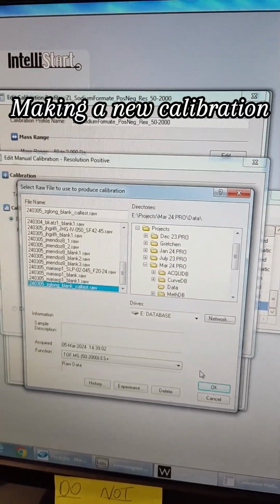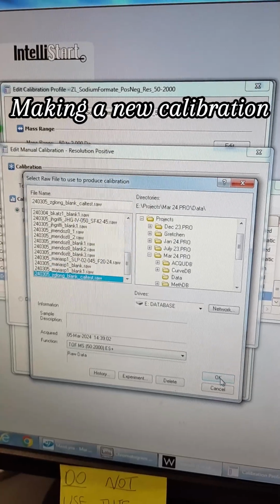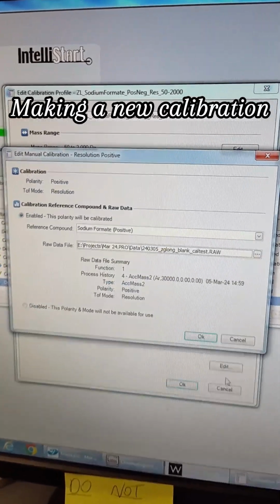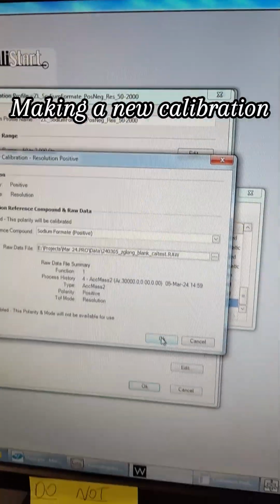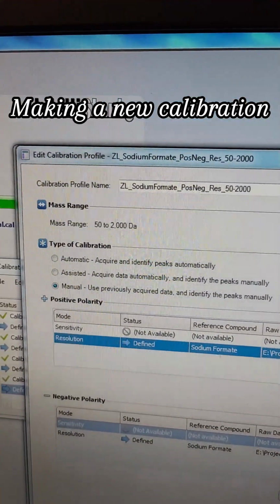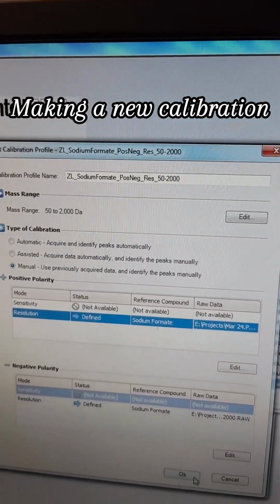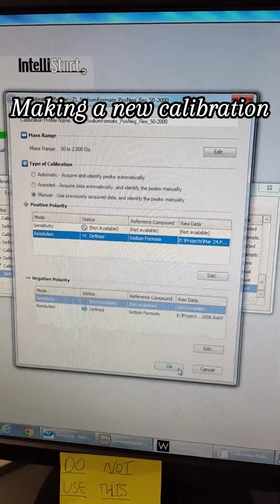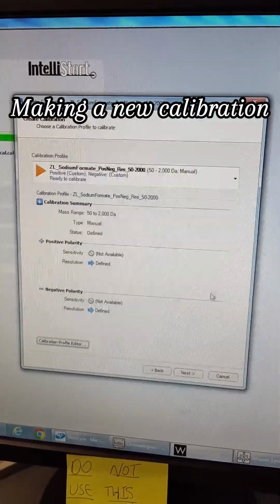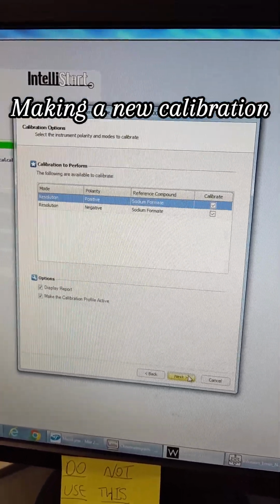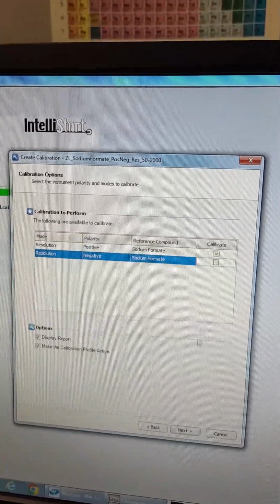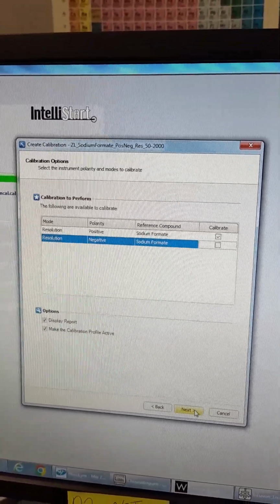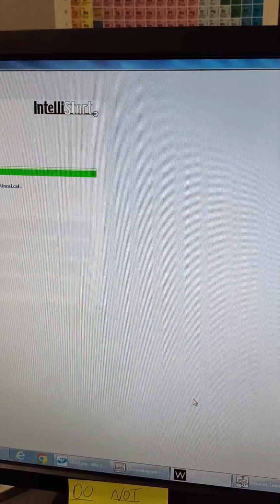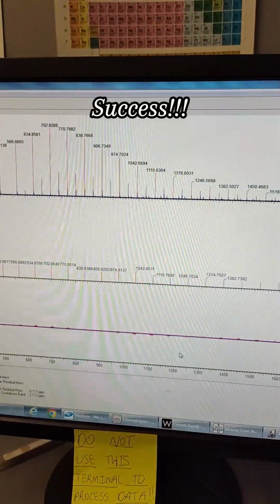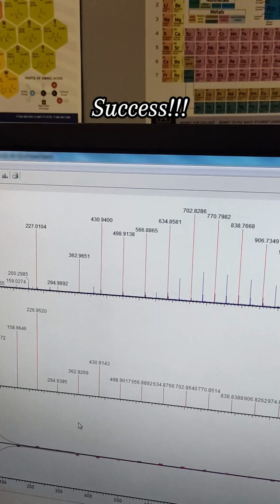And you can make sure that you find the file we just saved the spectrum for, and hit OK, and then that's going to be loaded with the sodium formate positive mode. Again, we're doing the manual, use previously acquired data and identify the peaks manually. So we're going to just hit OK and then close it and hit next, and then make sure you're just selecting the positive mode calibration to perform, and hit next and then start, and it should automatically go through the data and find all the peaks.